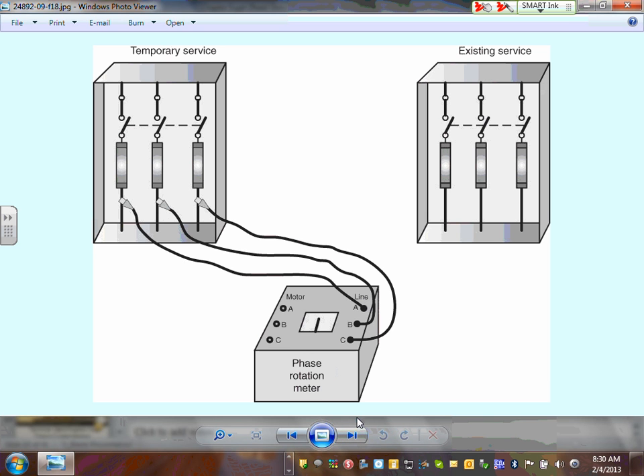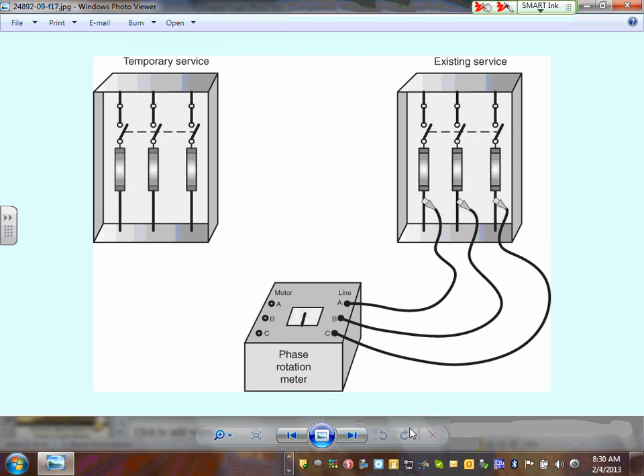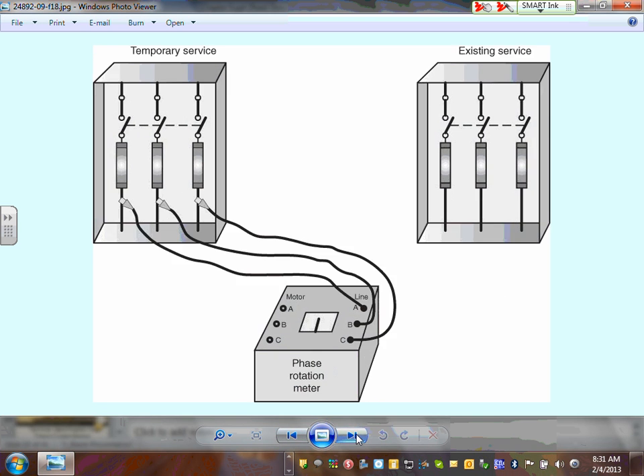You have to check the phase rotation. Absolutely. So you're going to go first to the existing, identify A, B, and C, and then you're going to go to the temporary, identify A, B, and C. If it doesn't give you correct, all you have to do is flip them, make A, B and B, A, and done. Flip any two phases.